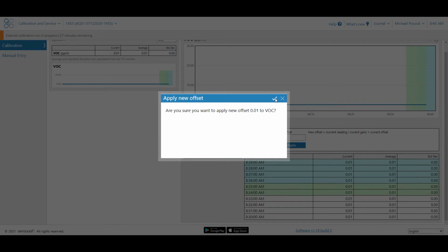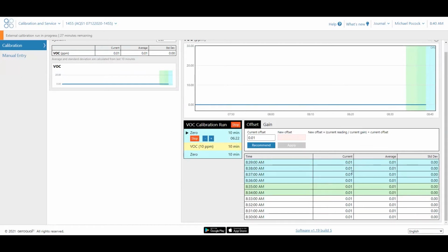Okay, so what that's done is that's just offset and made the instrument believe that it's reading 0. So if we just waited another minute, this would actually just change to 0.00 because I've just offset this reading. And so that's called changing your zero calibration. So you don't need to do that unless you have a number that's greater than plus or minus 1 ppm. So typically, it's not so common that you have to do this. The sensor is very stable and reads the zero reading very well.